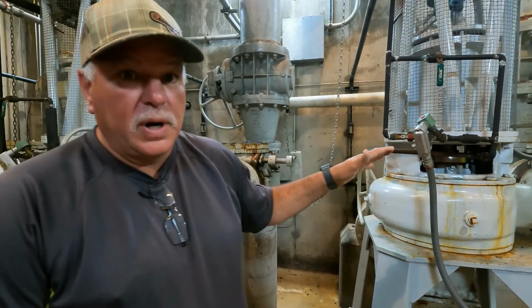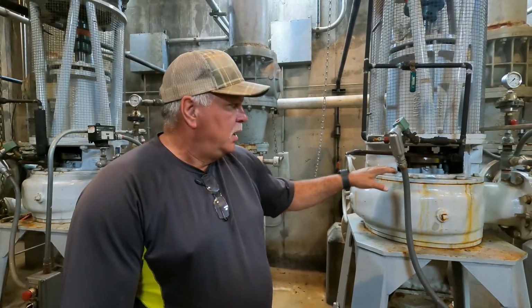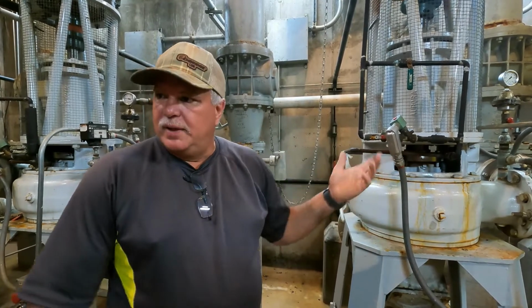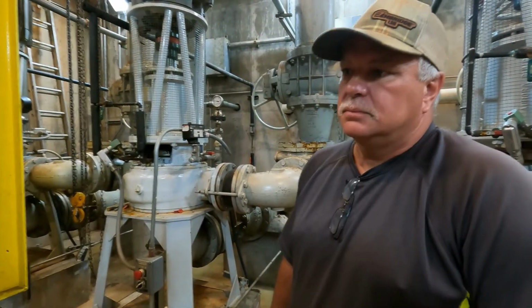So they're pumping in about a gallon a minute of fresh water or non-potable water to wash the seals. So if you did that 1,400 minutes a day, it's about to be a lot of gallons of water just to wash the seals over a month's time. So we use lake water 99% of the time. That eliminates your risk of having a cross connection.